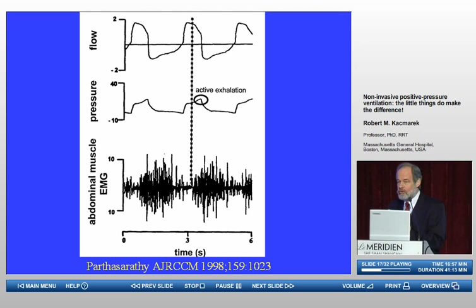And that primary variable, as you well know, is a decrease in flow to some specific percentage of peak inspiratory flow. Most ventilators have used 25% as the default criterion to allow transition to exhalation, which has worked very well in patients who were intubated and mechanically ventilated. But if the patient non-invasively chooses to end the breath at a flow rate that's higher than that 25%, what you will see is the patient forcing exhalation to occur.